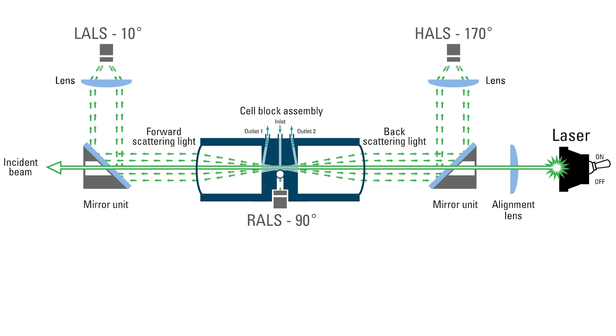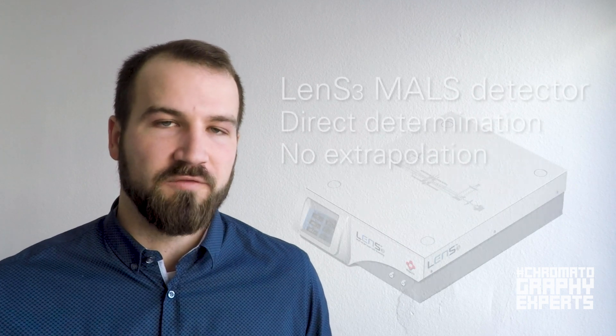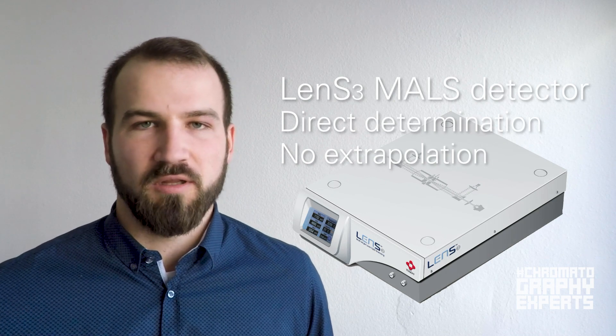You could also use a green laser with currently available conventional detectors, but this increases the noise by a factor of three as well, so the signal-to-noise ratio is not improved. With the LENS3, the angles at 10, 90, and 170 degrees allow us to do a direct measurement of molecular weight and a direct calculation of the radius of gyration without the need for the Zimm plot.